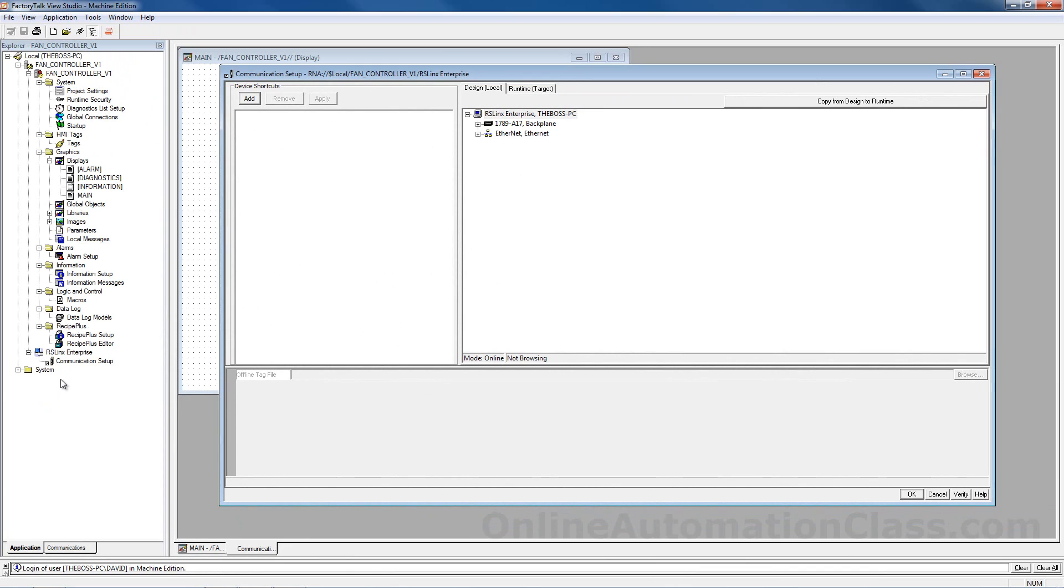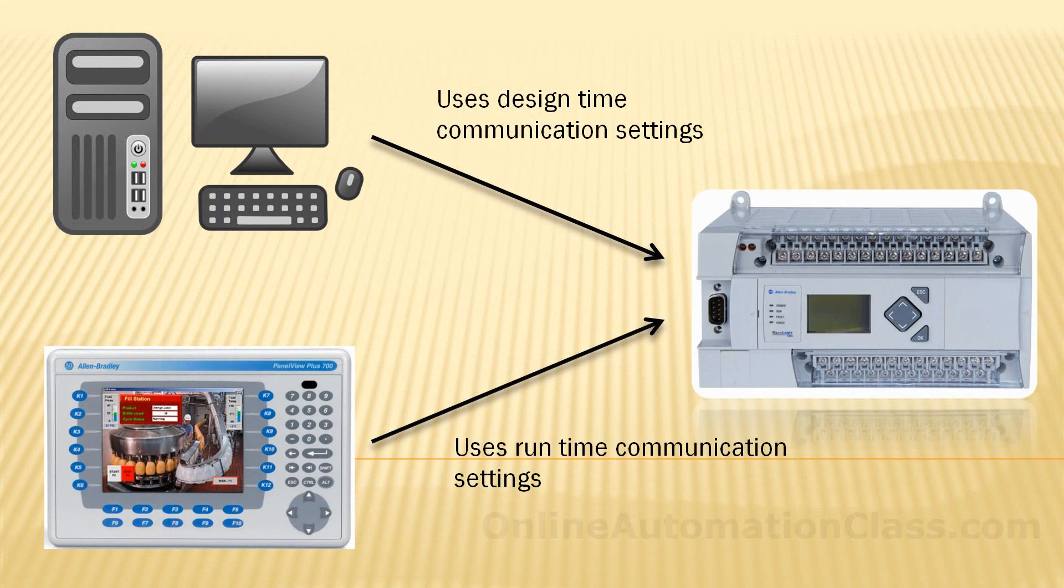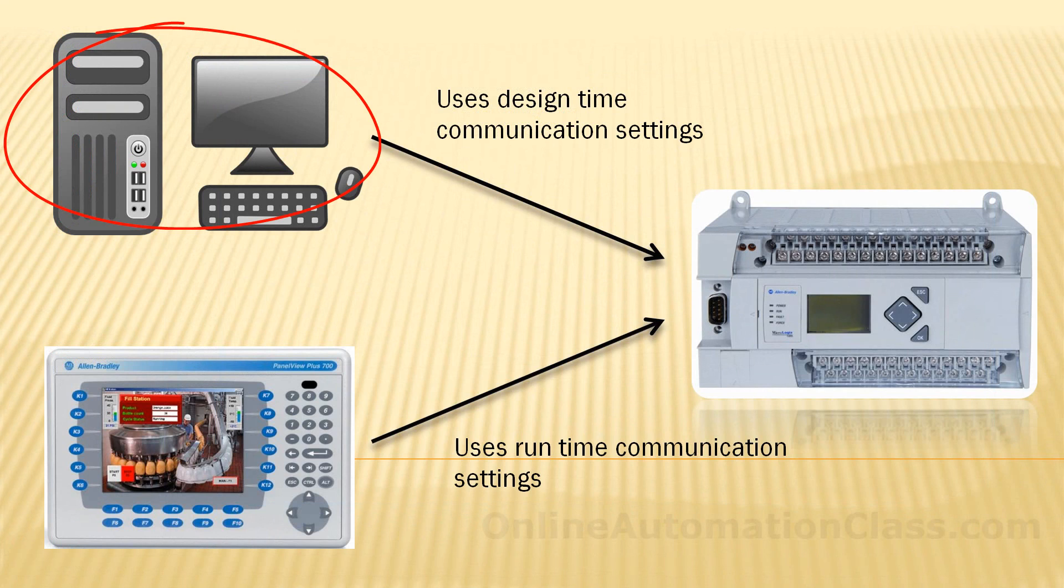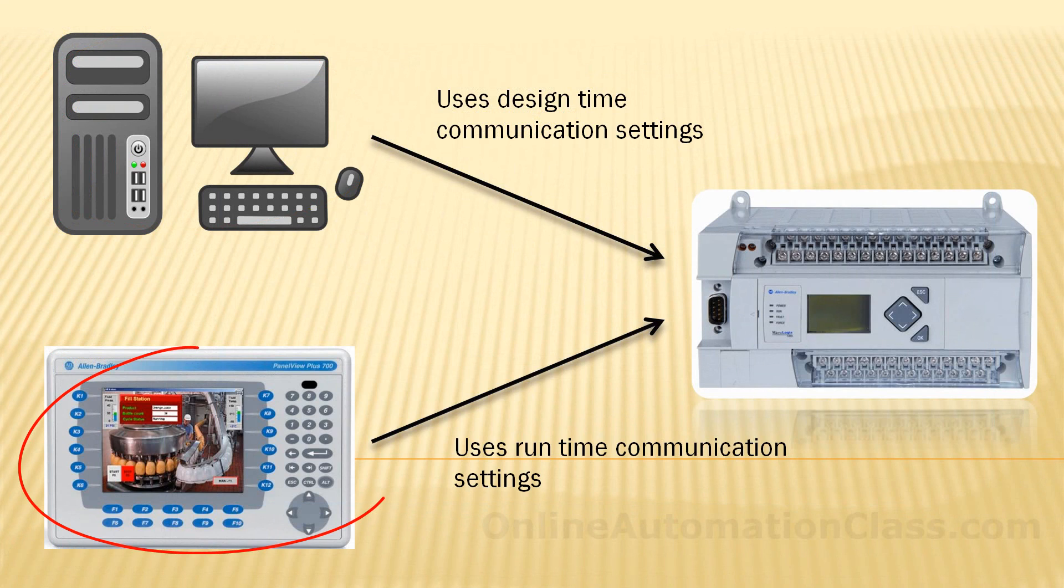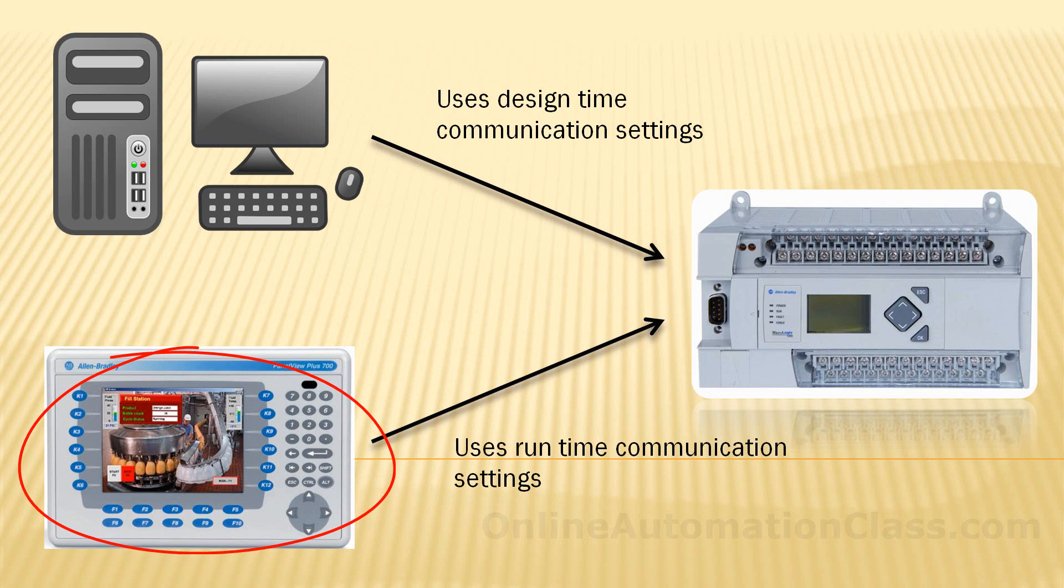There are two types of communication that need to be set up: design time and run time communication. Design time communication allows the HMI application to talk to the data source when it is running on the PC. When the application is downloaded into a PanelView Plus terminal, the application will use the runtime communication setting to talk with the data source instead of the design time communication setting.